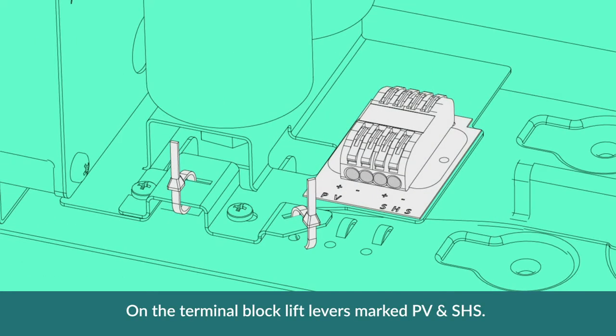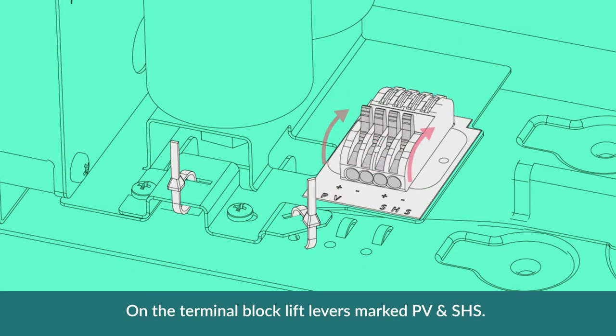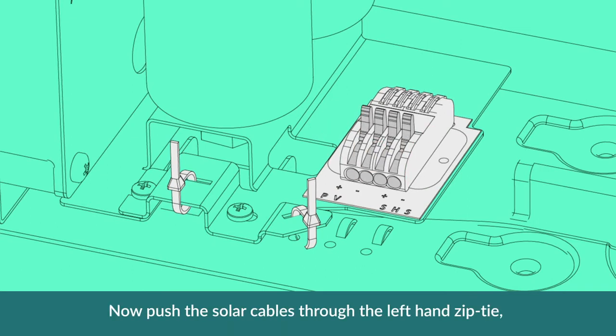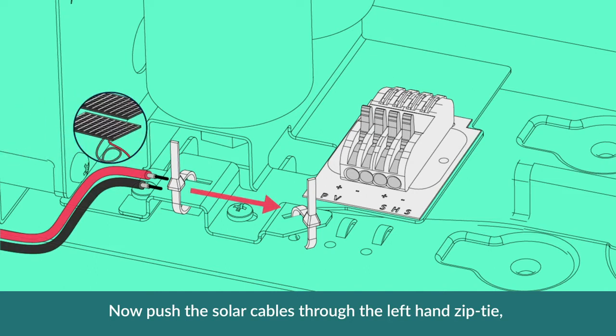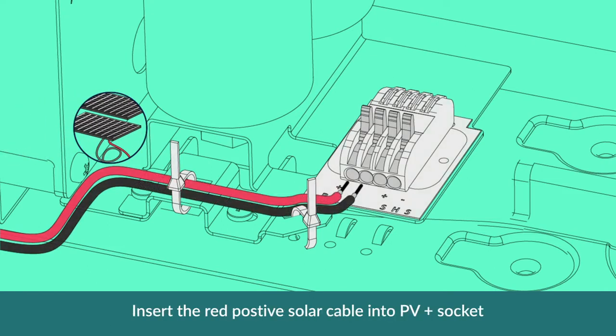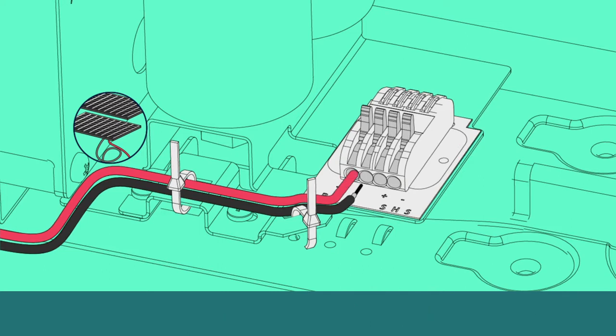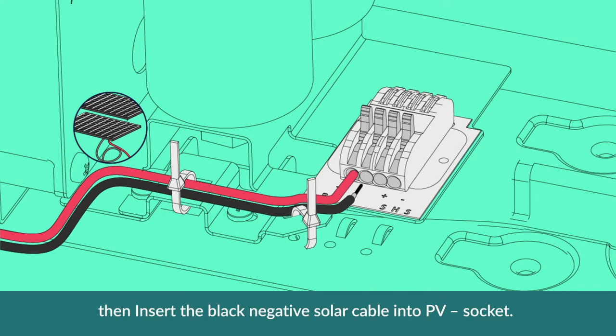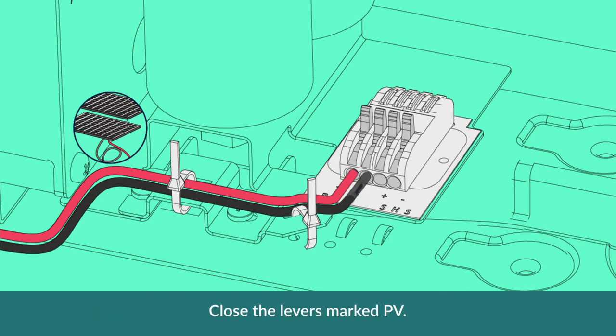On the terminal block, lift levers marked PV and SHS. Now push the solar cable through the left-hand zip tie. Insert the red positive solar cable into PV positive socket, then insert the black negative solar cable into PV negative socket. Close the levers marked PV.